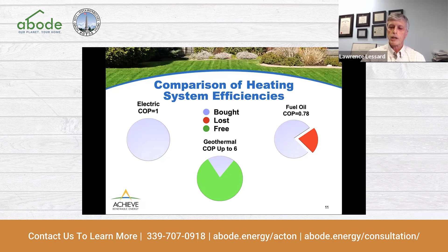Ground source turns the table on that, because remember, we're only paying for the piece of the pie that runs the equipment. The rest of the heat energy we get is from the ground. So, you know, in a sense, we're stealing it from the earth. So we get out much more than we put in. So the coefficient of performance can be up to 6 with the ground source heat pump. So we can get up to 6 times as much out as we put in. And that is why the equipment is so incredibly efficient, is because you're not making the heat, you're harvesting it, and you're harvesting it from someplace that has it as a resource. You don't have to make it.